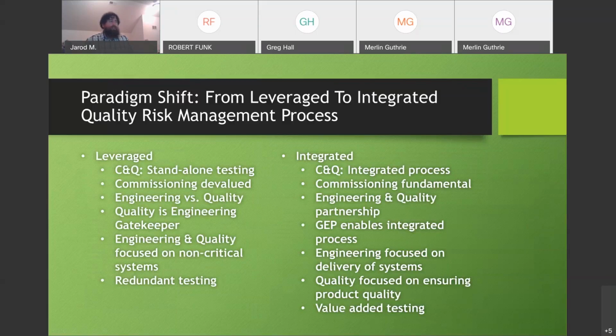From a leveraged process, commissioning and qualification were standalone testing. What would happen a lot is that commissioning activities occurring during the factory acceptance test would then be re-executed in the qualification process. Or a lot of times it would say, well, it was completed in FAT, so refer back to that execution.